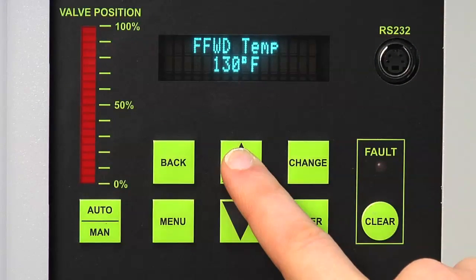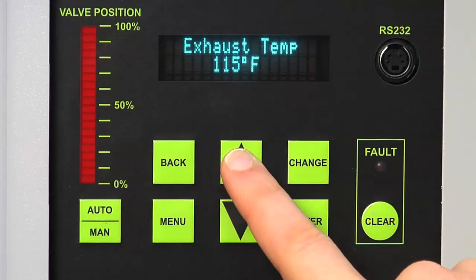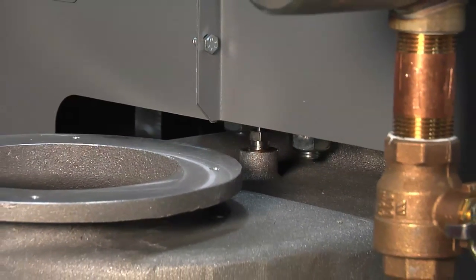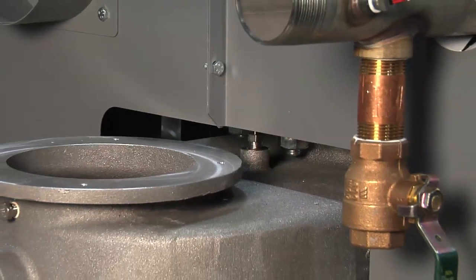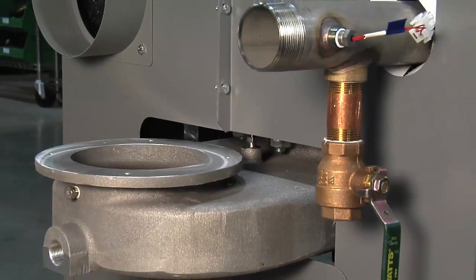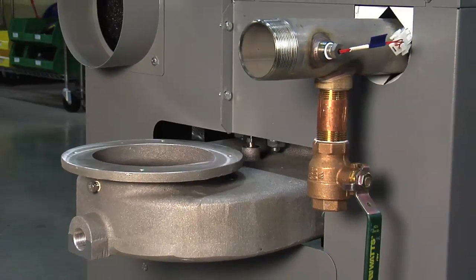This reduces service and maintenance costs far into the life of the product, as well as delivering optimal low-NOx combustion performance. The Innovation has an active exhaust gas sensor used to trigger maintenance alerts, trigger fire rate governor, and will lock out the unit to protect the heat exchanger and PVC flue installations.